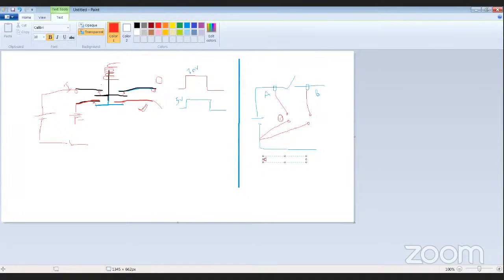So now, case number one, when the relay is open. So when the relay will be open, between point A and point C, I will write the voltage between A and C. If it is open, then this will be equal to... we were trying to see whether this switch is open or closed. So we need to attach two voltage sensors for each relay, and we need to see the voltage at these two points before the relay and after the relay. Based on this voltage, we can estimate whether the relay is closed or open.